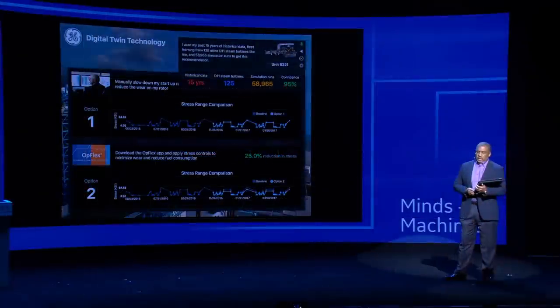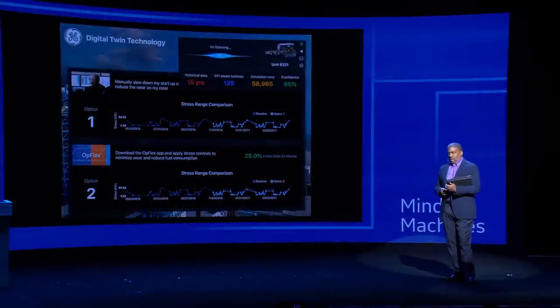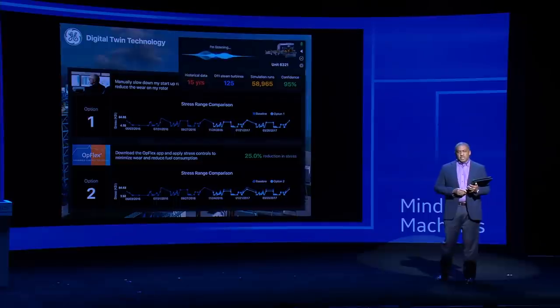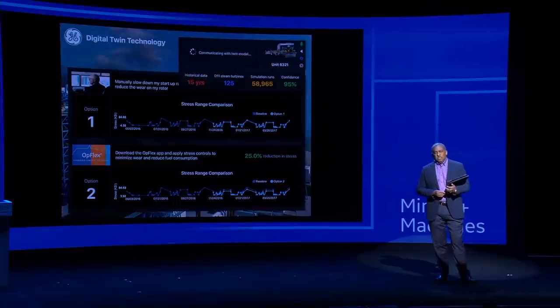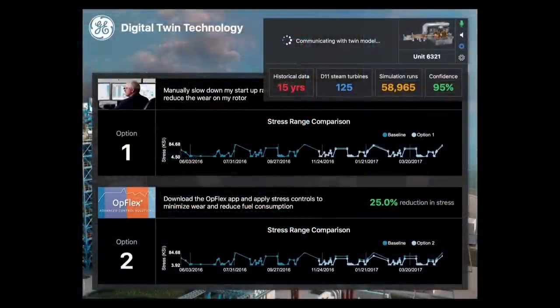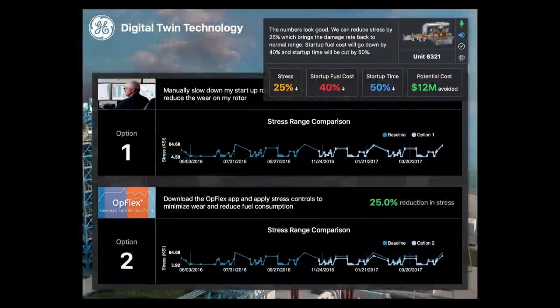Twin, I need a financial perspective. Tell me about the numbers. The numbers look good. We can reduce stress by 25%, which brings the damage rate back to normal range. Start-up fuel cost will go down by 40%, and startup time will be cut by 50%. You will also avoid $12 million by preventing an unplanned outage.